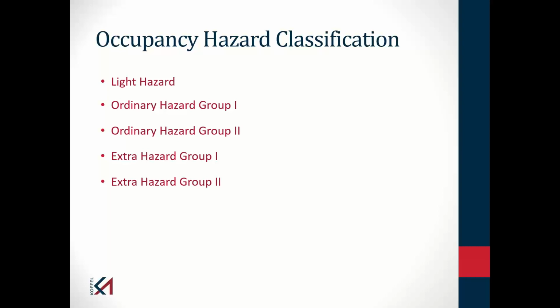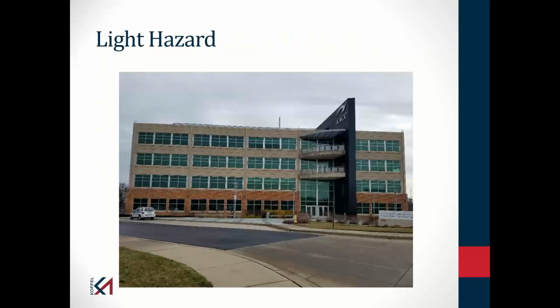And these hazard classifications affect things like the duration of your water supply, the density that needs to be delivered to control the fire, so the overall quantity of water that you need for the sprinkler system. It will affect the spacing of the sprinklers. In some cases, it actually affects whether you can use a certain type of sprinkler or whether you may be required to use a certain type of sprinkler. Now, for other than storage occupancies, NFPA 13 identifies 5 different hazard classifications. Many of your facilities, the spaces within those facilities are going to be what's considered a light hazard. We have a low quantity of combustibles, relatively low heat release rates.